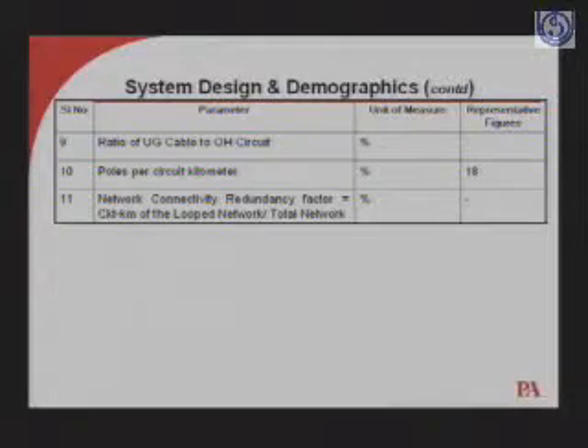So, the ratio of underground cable to overhead circuit. All of you understand what underground cable is. It is there especially in the metros like Mumbai, Calcutta, Ahmedabad, Delhi, in some, Pune, not, I am not very sure, where underground cable is there, and overhead lines are there. The more the underground line, the more is the possibility of giving stable and quality power supply to the people. But at the same time, if there is a fault, it will take longer to restore the supply, and therefore you have to have a looped network, a ring main circuit, so that if one section is faulty, through the other section you can restore the supply.